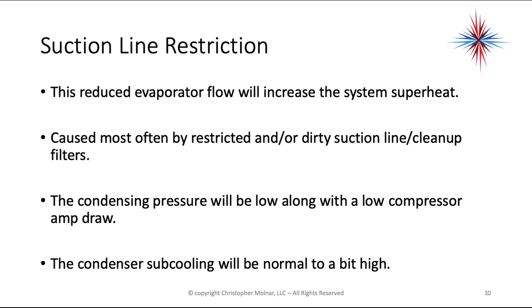Suction line restrictions are caused most often by restricted or dirty suction line cleanup filters. The condensing pressure will be low, along with low compressor amp draws. The condenser sub-cooling will be normal to a bit high.